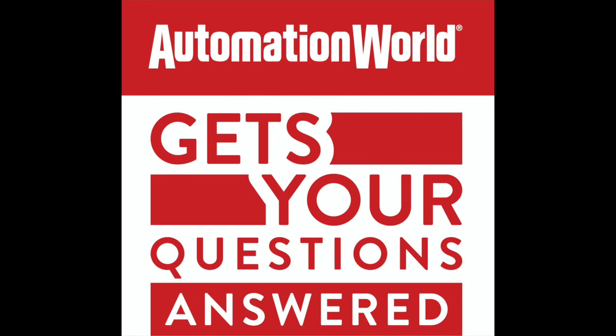Yeah, great question. So on this one, one of the issues that I've seen come up sometimes when looking at MTTR and MTBF is focusing too much on each of those numbers in a silo without necessarily thinking about how it's affecting other things. One of the things that I've noticed is assets that might have, for example, a relatively low MTBF and a low MTTR are said to have a problem with microstops, right? That's saying a low MTBF means low time between failures, so failures are happening frequently, but low MTTR, where maybe the fault corrects itself or it's a very quick maintenance operation to get things back up and running.